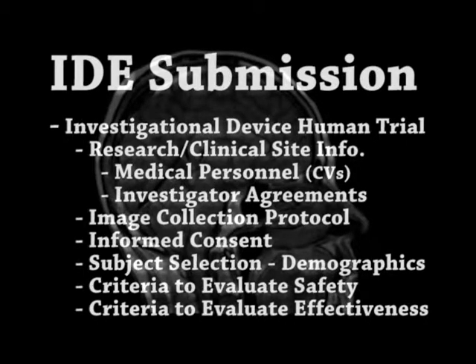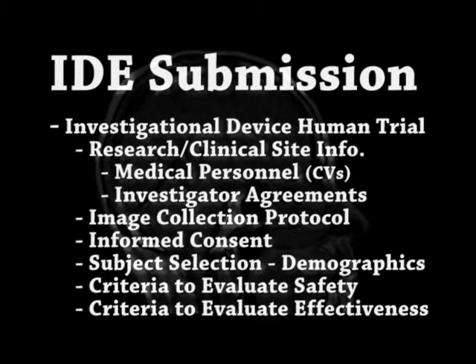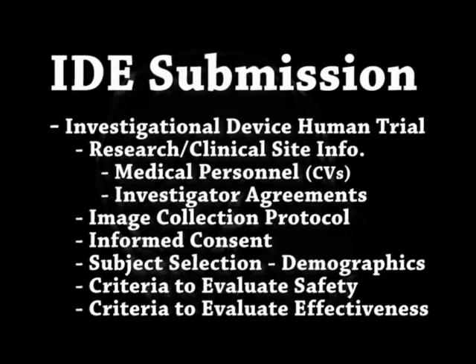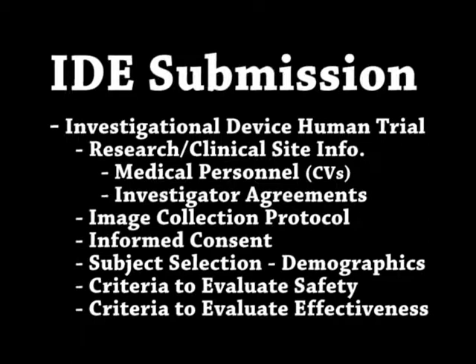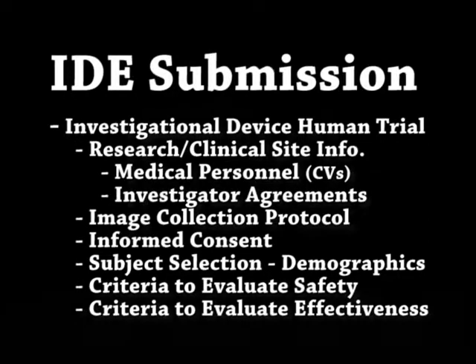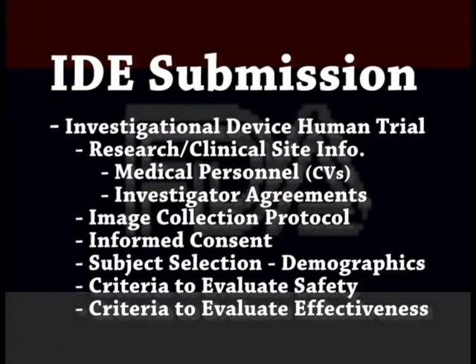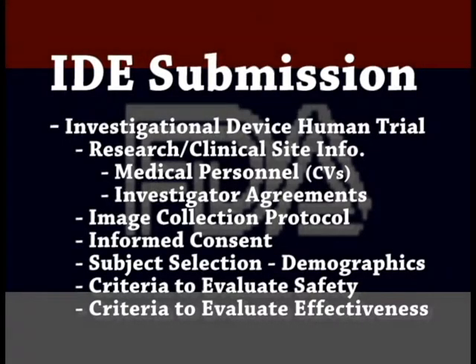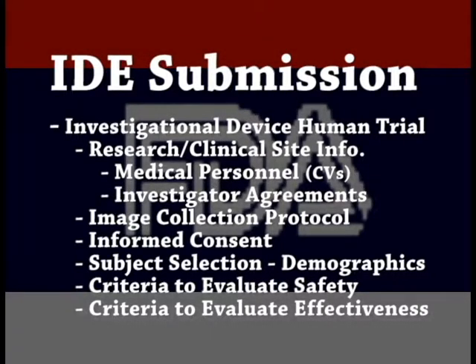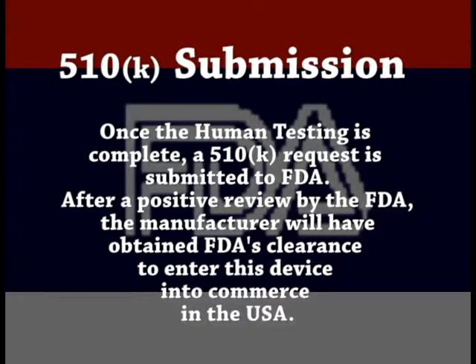The FDA needs information about the site where the device will be operated, CVs of the medical and technical personnel involved, and their affiliations and function in the trial, including signed investigator agreements to follow the written protocol during the clinical testing. Subject selection methods and demographics will be described. The informed consent document that volunteer subjects will read and sign is included. If there is a university affiliation, a local IRB, that's the Institutional Review Board, their approval of the research trial should be included. The protocol involves criteria for evaluation of safety and effectiveness. All the information is submitted to the FDA in order to have authorization to begin human testing of the new investigational device. Once the human testing is complete, the next step is submission of a 510K to the FDA.